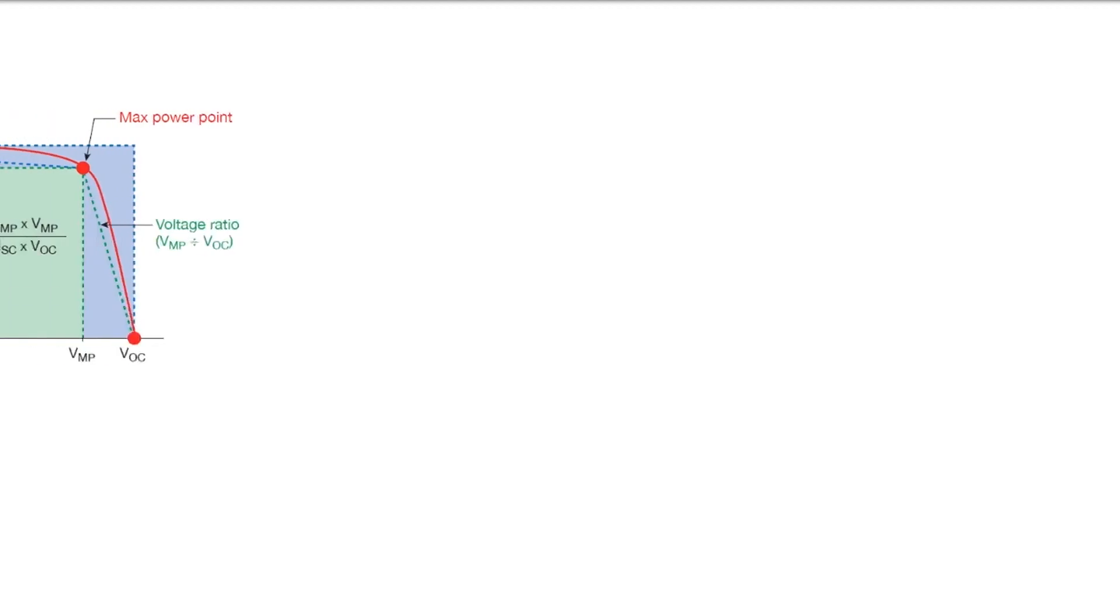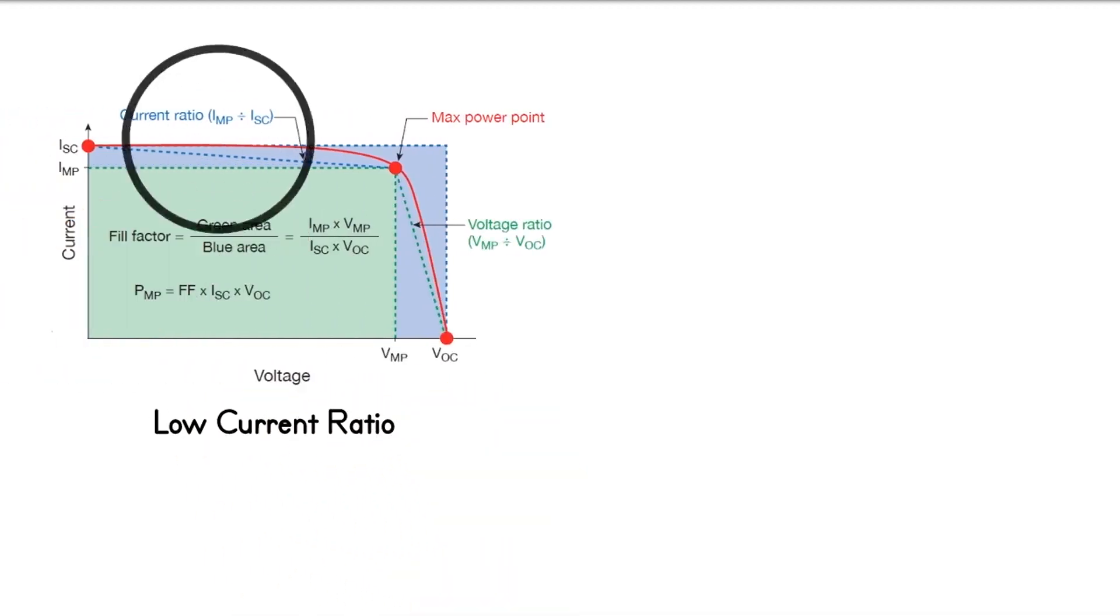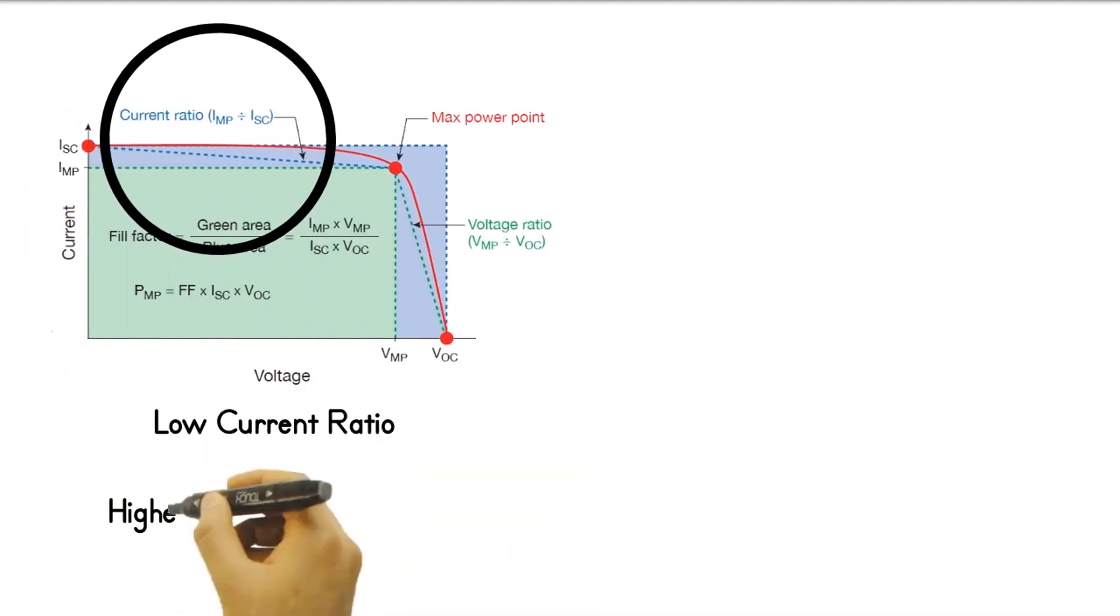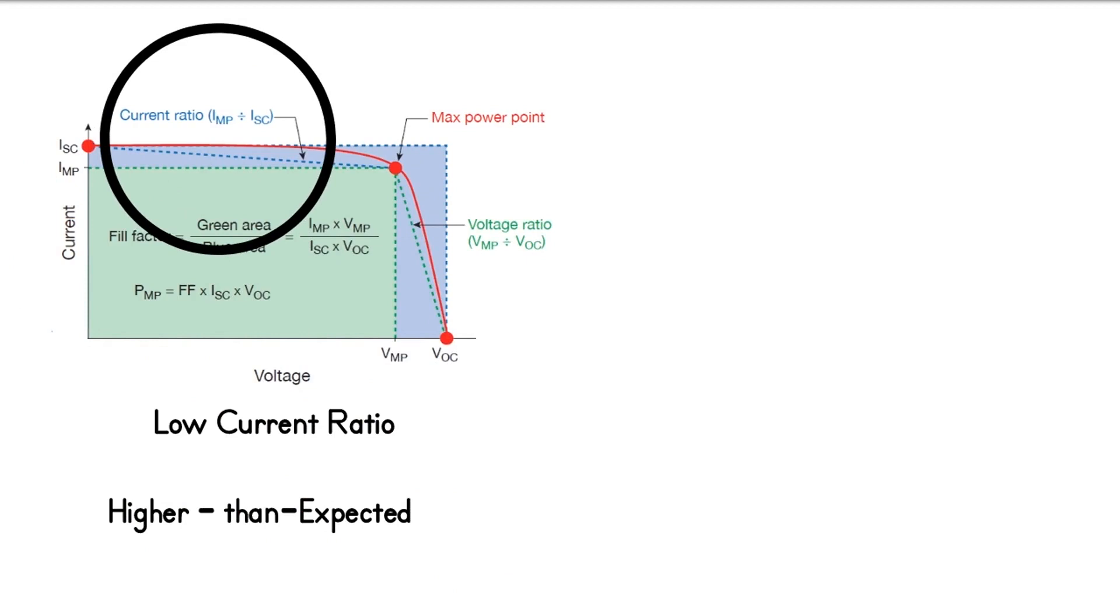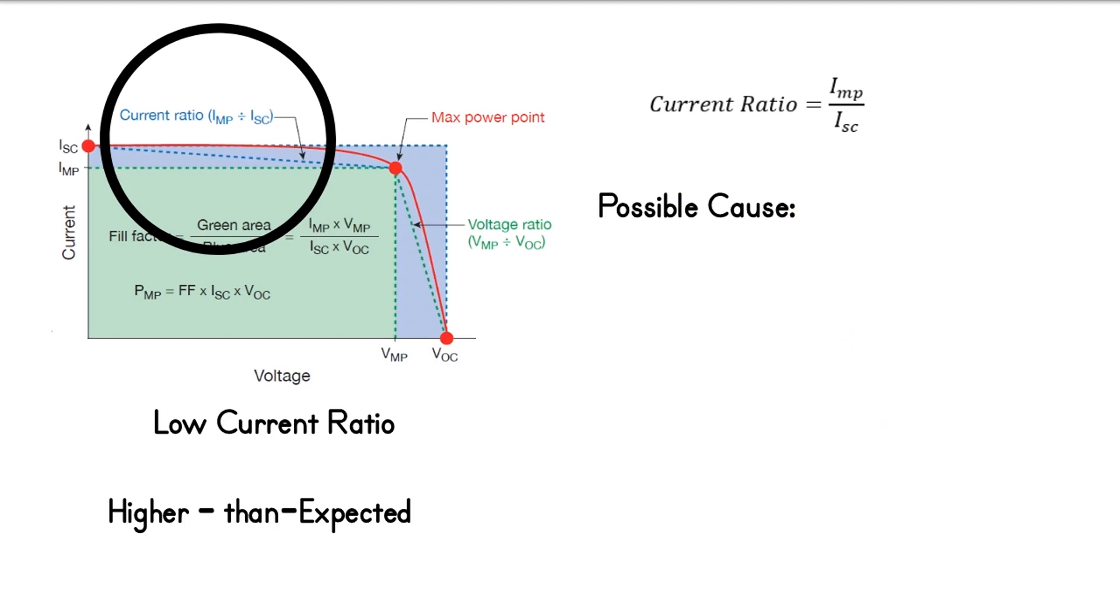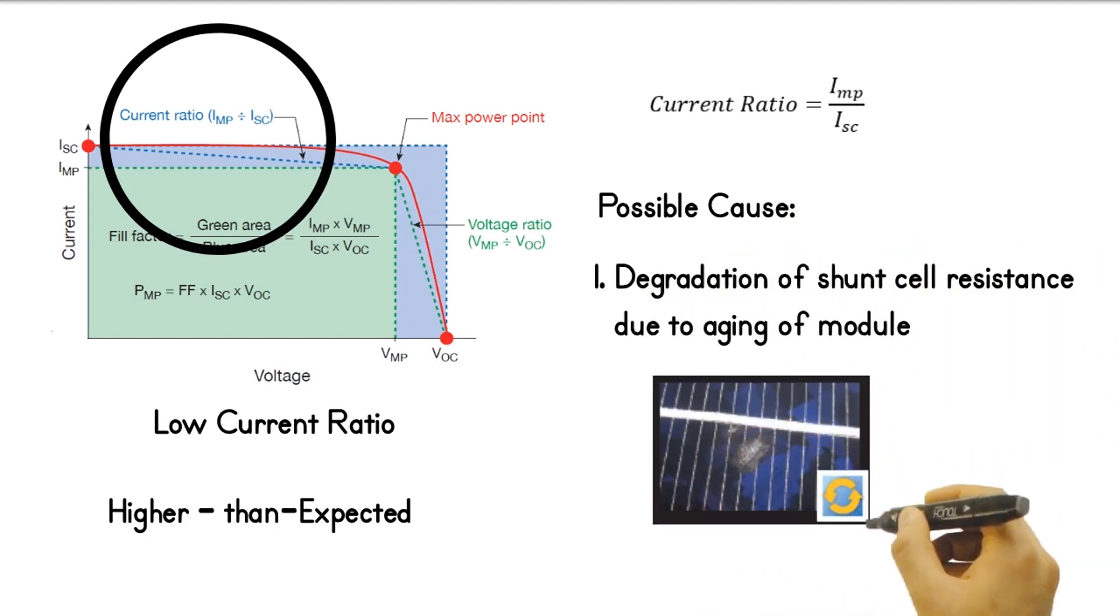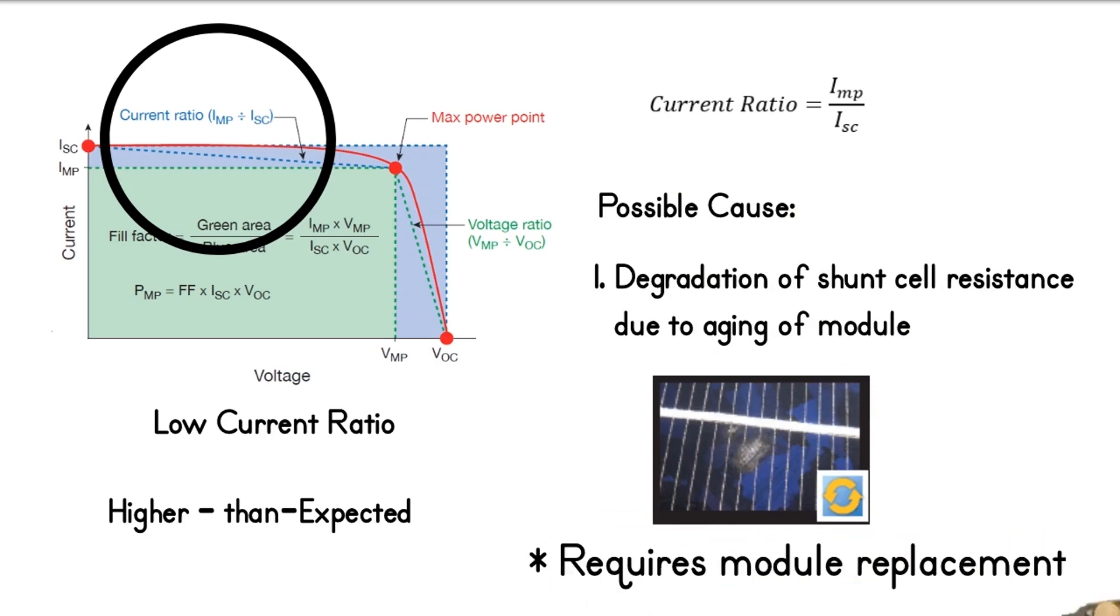The sixth type of deviation is low current ratio, and is characterized by higher than expected horizontal portion of the IV curve. It is calculated as the current at maximum power point IMP divided by the short circuit current ISC. Low current ratio is more likely caused by the degradation of cell shunt resistance, which occurs as the module ages. This may require module replacement.